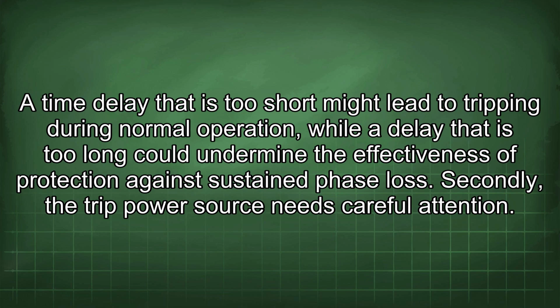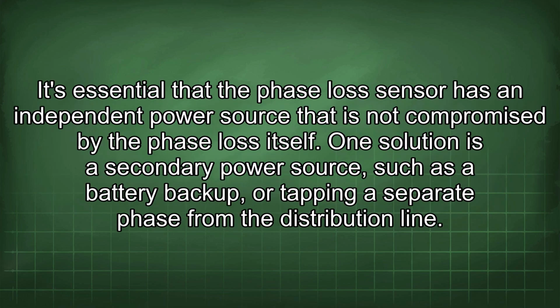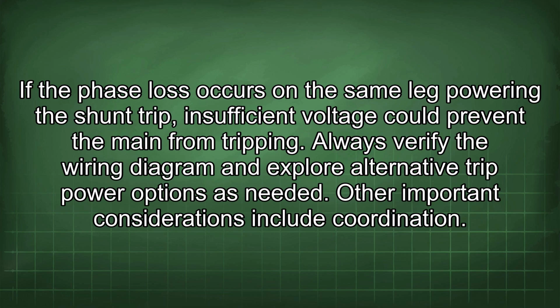Secondly, the trip power source needs careful attention. It's essential that the phase loss sensor has an independent power source that is not compromised by the phase loss itself. One solution is a secondary power source, such as a battery backup, or tapping a separate phase from the distribution line. If the phase loss occurs in the same leg powering the shunt trip, insufficient voltage could prevent the main from tripping. Always verify the wiring diagram and explore alternative trip power options as needed.